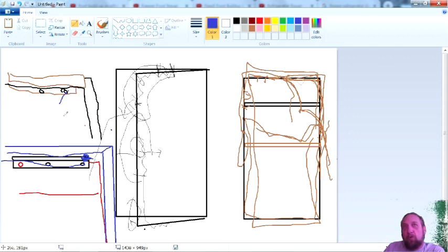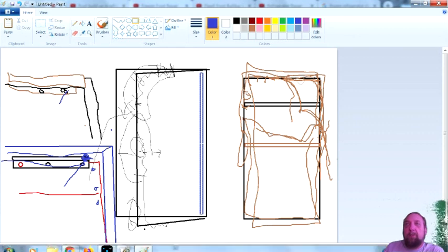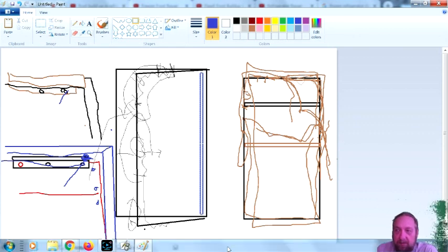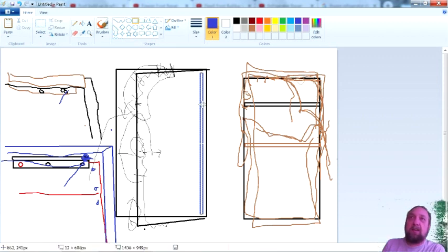So they went from screw holes to metal support to removing the metal support and just putting the screw holes in the plastic liner, to eventually now inside the door there was just a small metal channel. And the metal channel, the gasket just pushes in. I think every single one of the refrigerators in my class now are all just push the gasket into the groove. There is no glue. There is no adhesive. There are no screws. You just pull the gasket out and tuck the new one in. And when it goes inside this channel, it gets pretty tight. So the channel is all the way around the door here and holds the gasket all the way around.